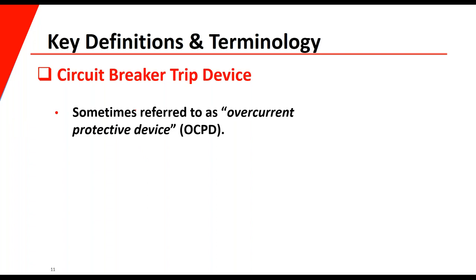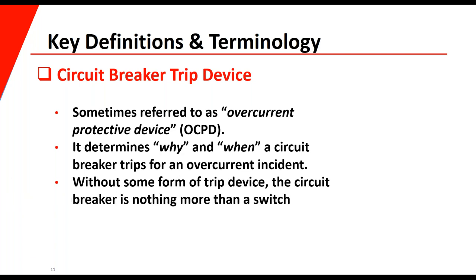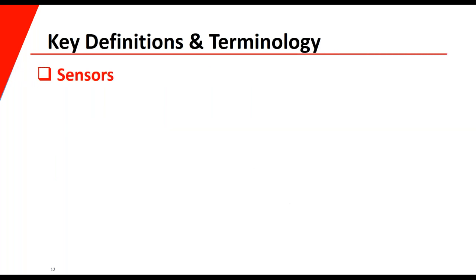The circuit breaker trip devices, sometimes referred to as overcurrent protection devices or OCPDs, determine why and when a circuit breaker trips for an overcurrent incident. Without a trip device, the breaker is nothing more than a switch. With a trip device, we can protect the circuit from an overcurrent incident and trip the breaker at a given time.